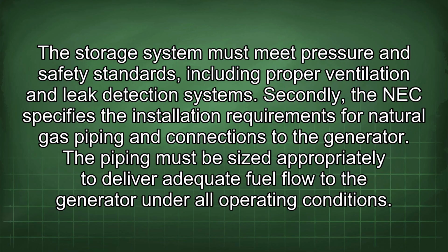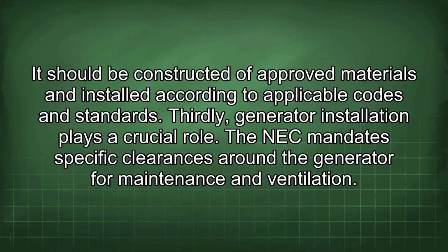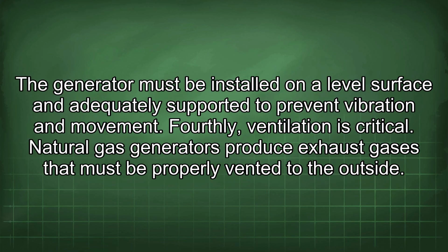Secondly, the NEC specifies the installation requirements for natural gas piping and connections to the generator. The piping must be sized appropriately to deliver adequate fuel flow to the generator under all operating conditions. It should be constructed of approved materials and installed according to applicable codes and standards. Thirdly, generator installation plays a crucial role. The NEC mandates specific clearances around the generator for maintenance and ventilation. The generator must be installed on a level surface and adequately supported to prevent vibration and movement.